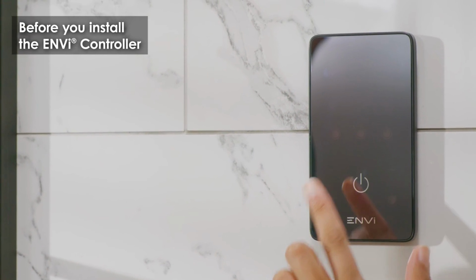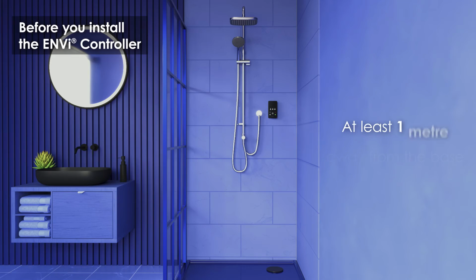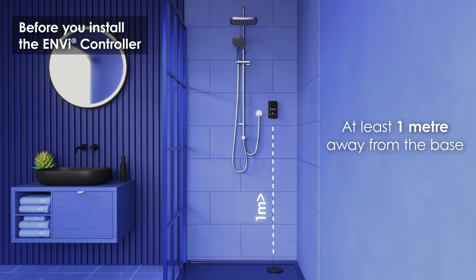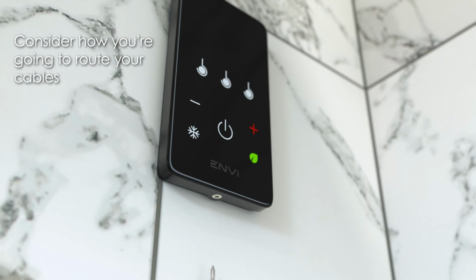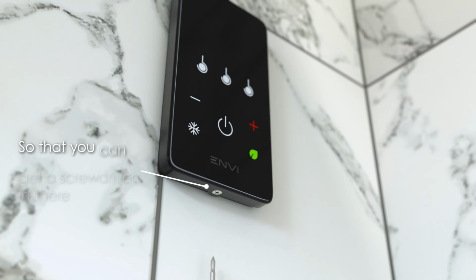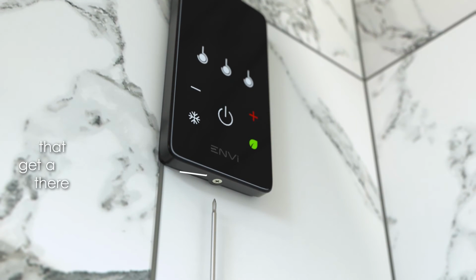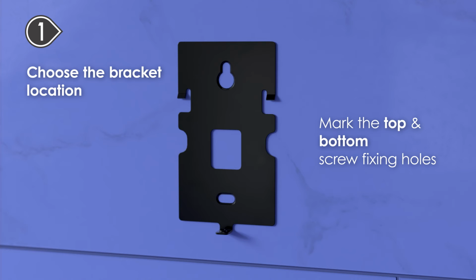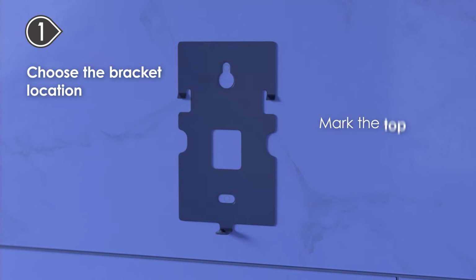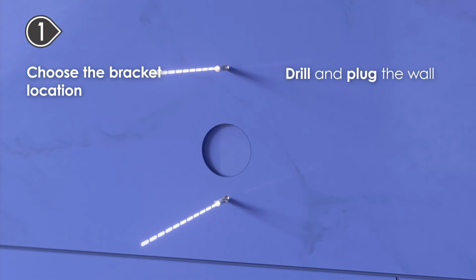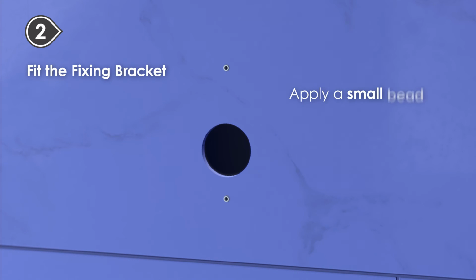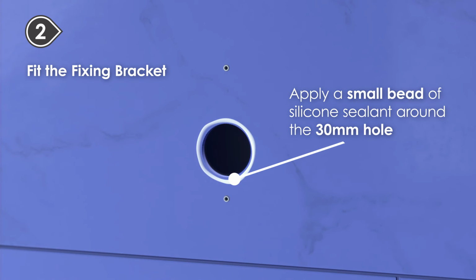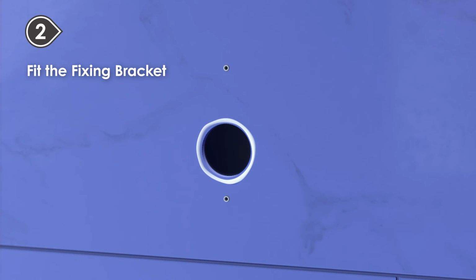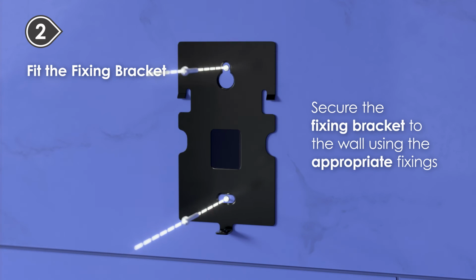When it comes to the placement of the ENVi controller, make sure it's at least a meter away from the base. For your controller, consider how you're going to route your cables and the clearance you need below so that you can get a screwdriver in there. Once you have a location for the fixing bracket, hold it in position and mark the top and bottom screw fixing holes. Then remove the bracket from the wall and drill and plug the wall for your fixings. Apply a small bead of silicone sealant around the 30mm hole. This will help you seal the bracket to the wall. Secure the fixing bracket to the wall using the appropriate fixings.